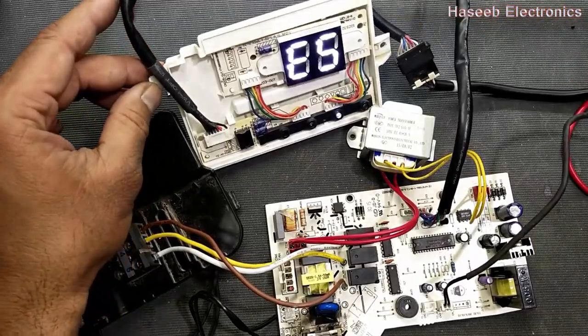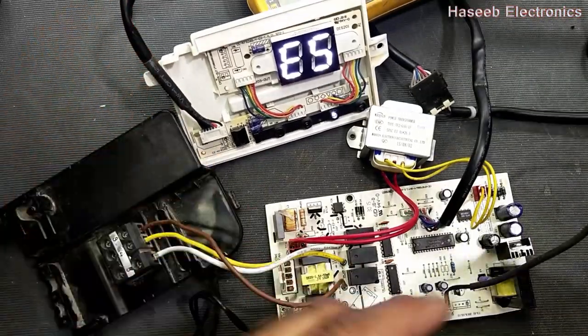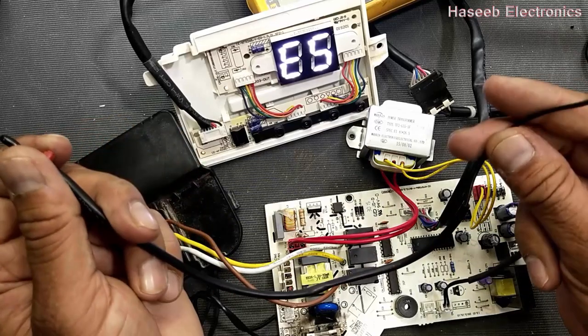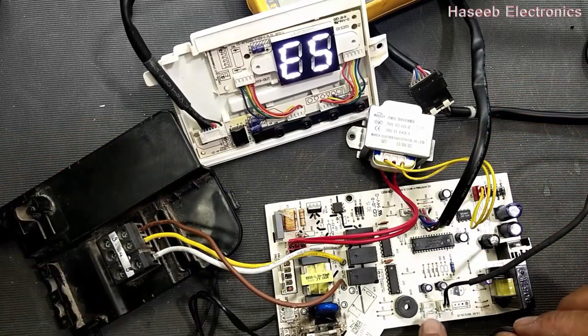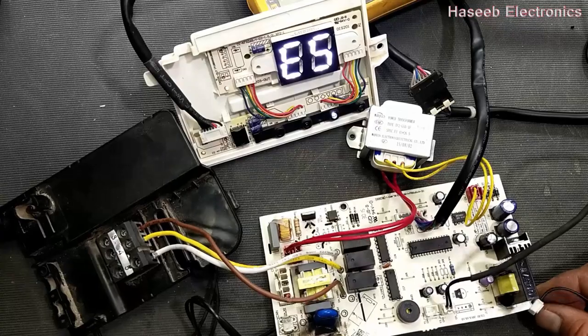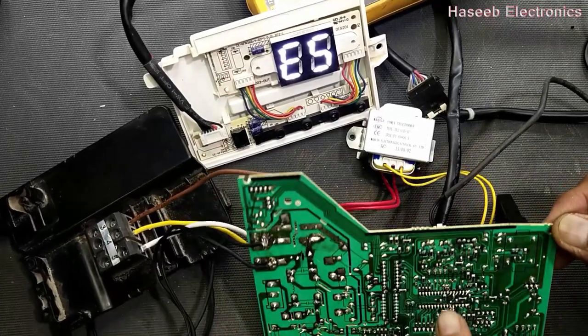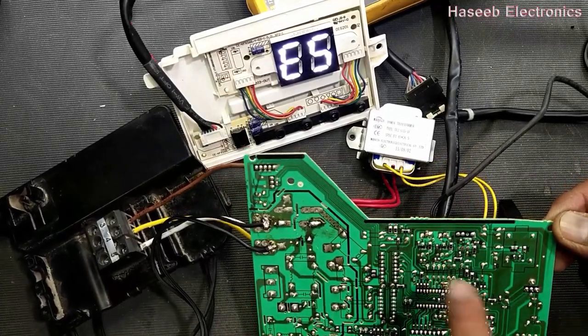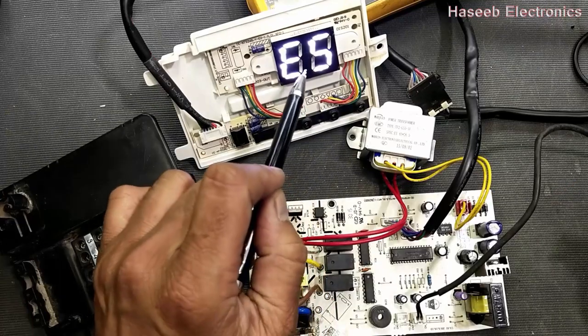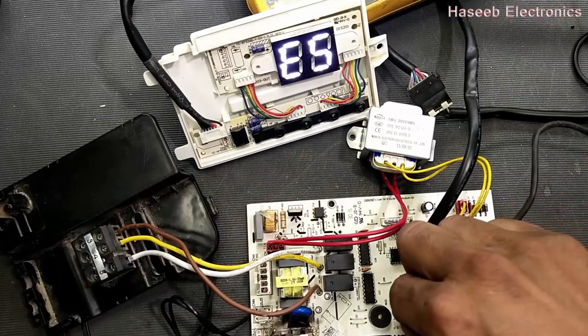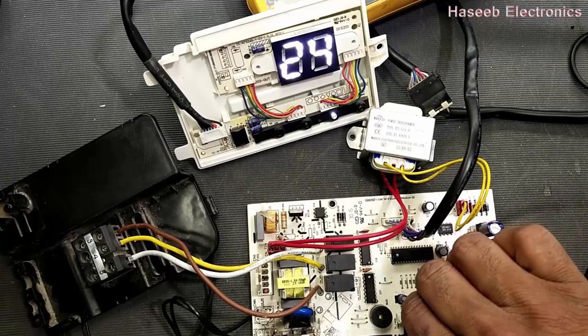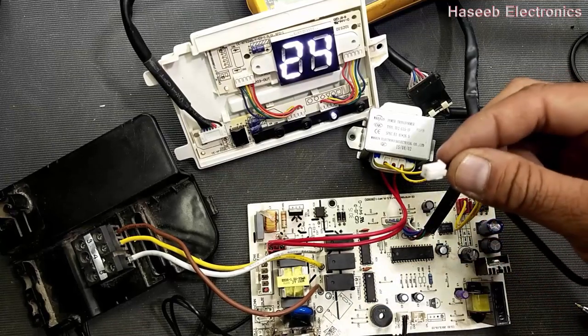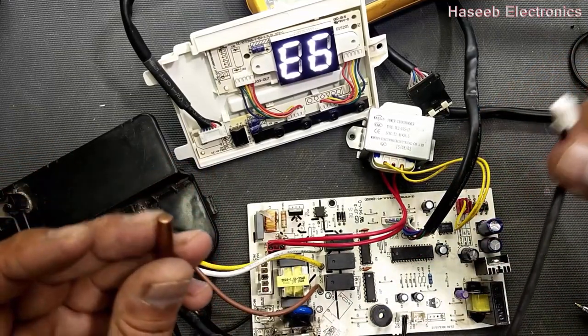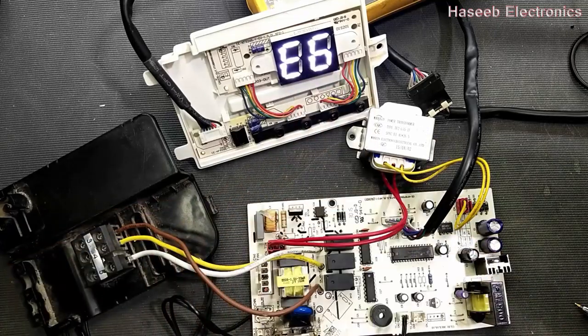E5 error. That means the room temperature sensor, or its cable or connector, or maybe a transistor at this point. The light will blink and it will display E5. Now I am going to connect the sensor. If I remove this pipe temperature sensor, it will generate an E6 error.